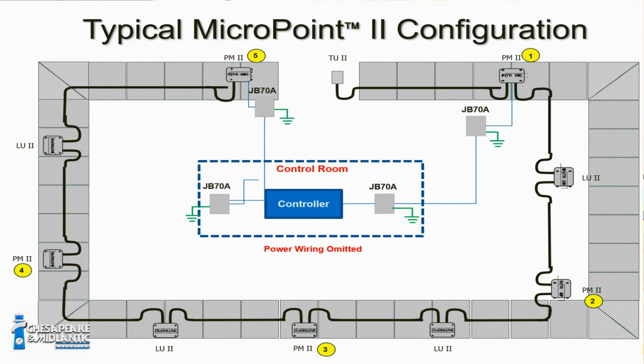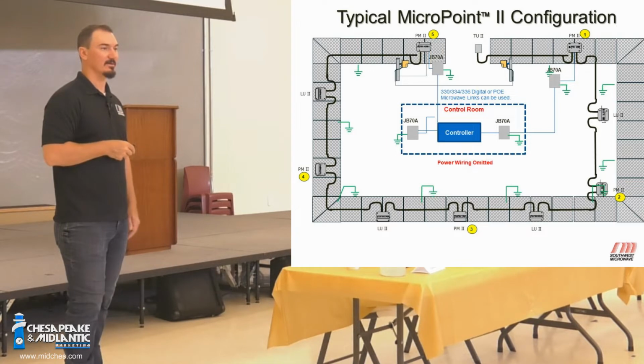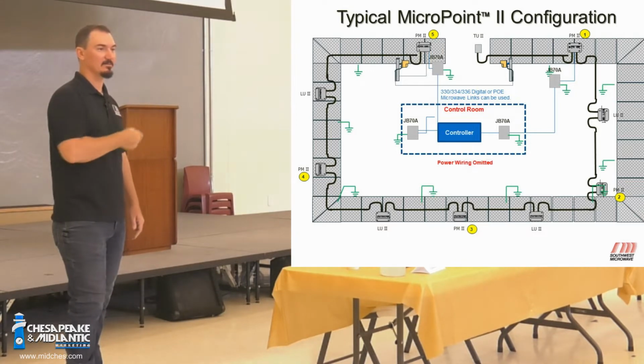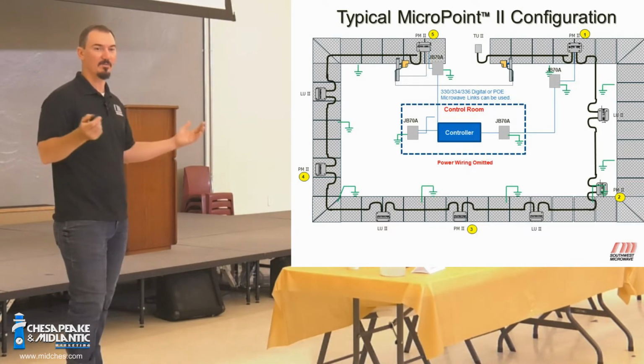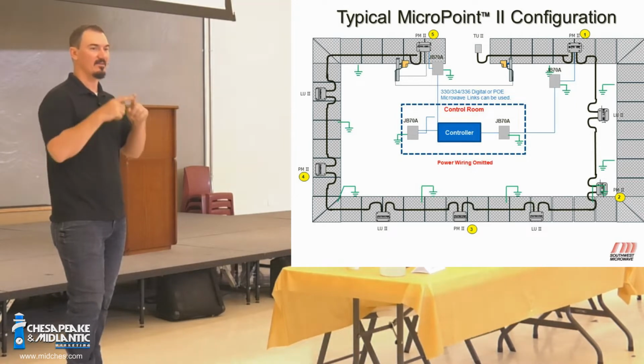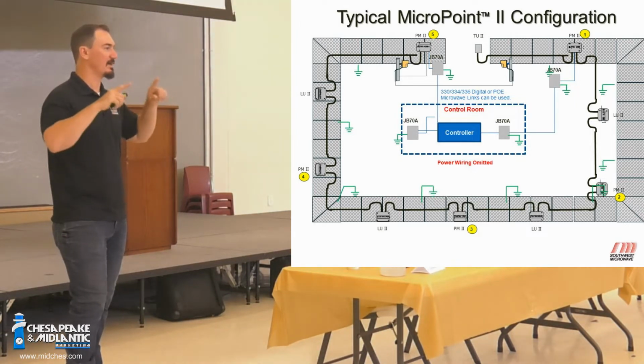So power and data come from the control room, out around the perimeter, back into the control room. We call this the fault tolerant loop. One thing you want to be checking on when you're designing new systems is this fault tolerance. That way, if someone were to cut the cable, shoot a processor, blow up a box, something like that, you still have power and data around the perimeter. This is bidirectional.